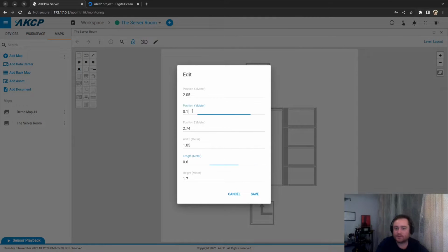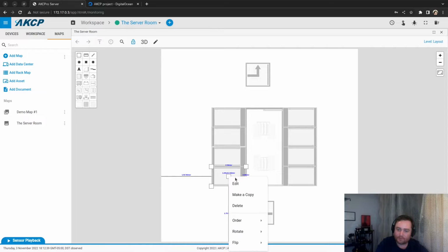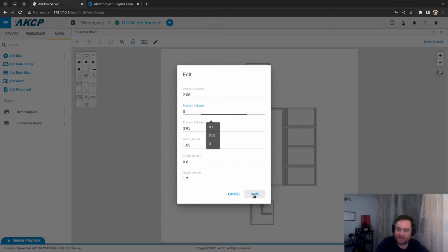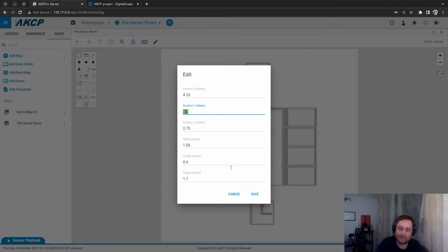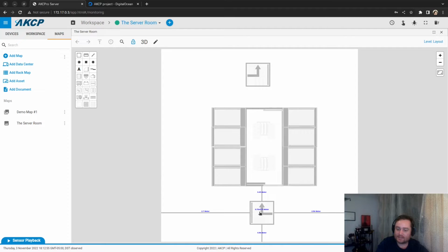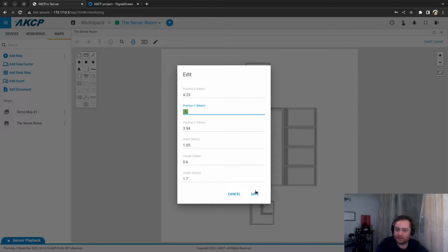when the person that will use the software draws the room, his first instinct will be to not put the gap under the rack. So you will have your probe set, and your probe will detect a mixing of air. So the air won't enter your rack at the same temperature as your CRAC made them. So, for example, the air exits the conditioning unit at 20 degrees Celsius and goes under, and it will enter the rack at 22. So yeah, something happened between the two. But the person that drew the room drew it without the gap, and there is really a gap.